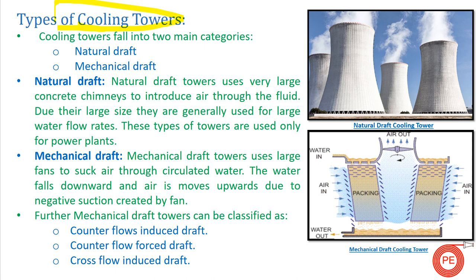There are two broad types of cooling towers: natural draft and mechanical draft. Natural draft cooling towers are very large concrete chimneys through which air is introduced, and a large amount of fluid needs to be cooled. You would have seen these in power plants, nuclear power plants, and other industries where a large amount of water needs to be cooled.